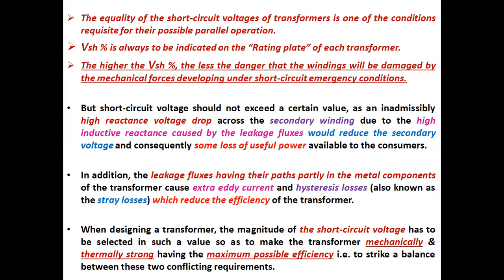But short circuit voltage should not exceed a certain value, as an inadmissibly high reactance voltage drop across the secondary winding due to the high inductive reactance caused by the leakage fluxes would reduce the secondary voltage and consequently cause some loss of useful power available to the consumers.